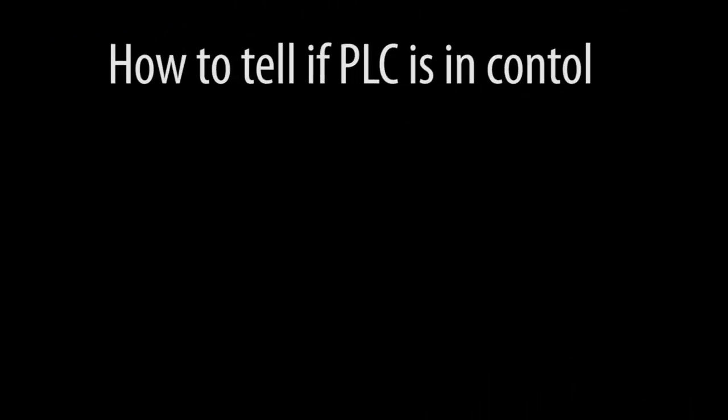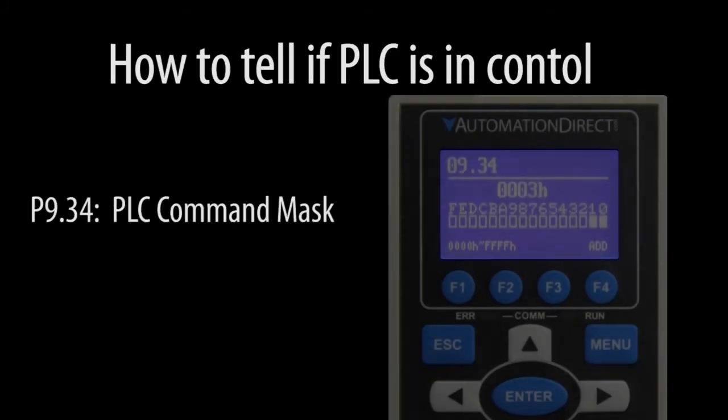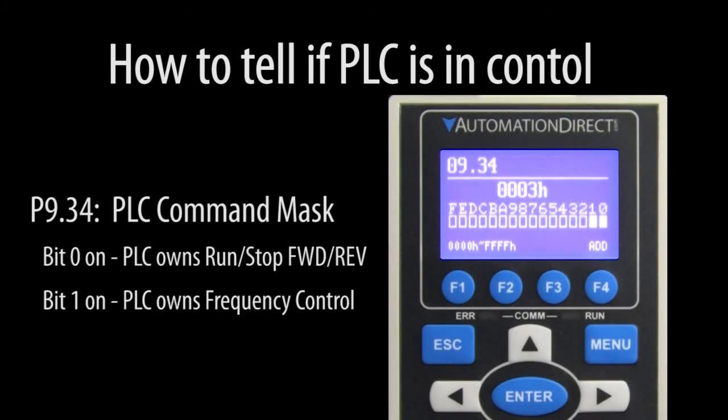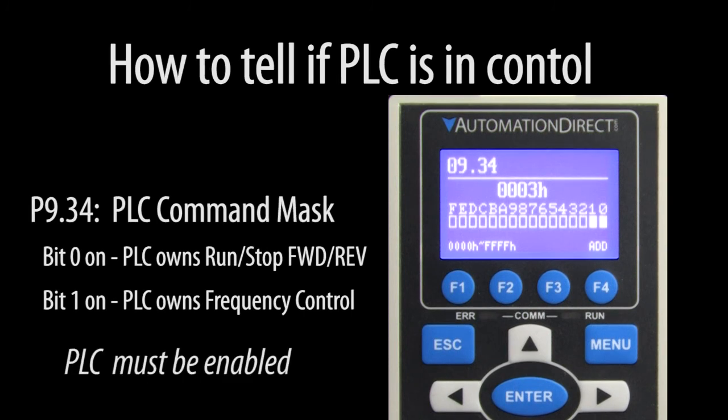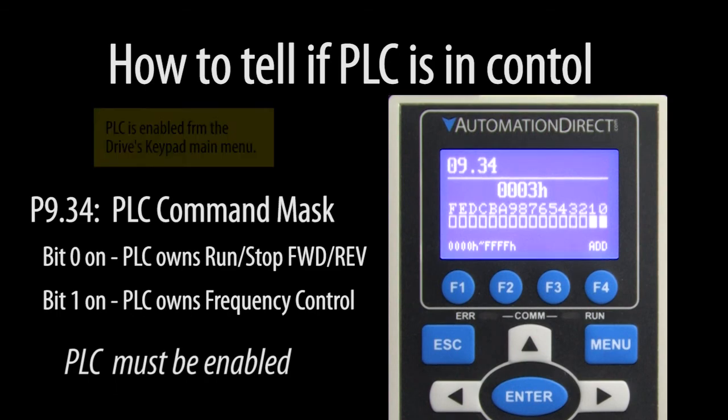If you have any question about whether the PLC or the drive owns the frequency or the controls, parameter 934 shows you what the drive thinks the PLC is controlling. Remember, these will only be lit up if the PLC is enabled.